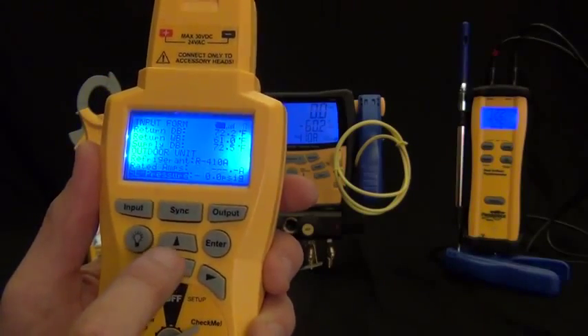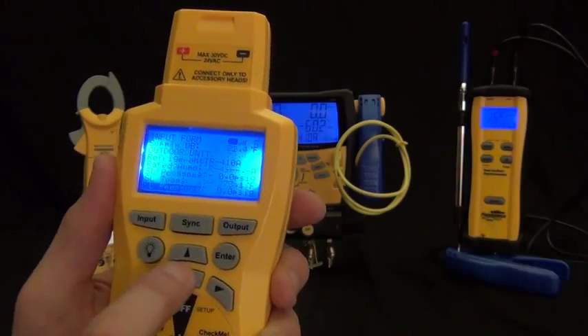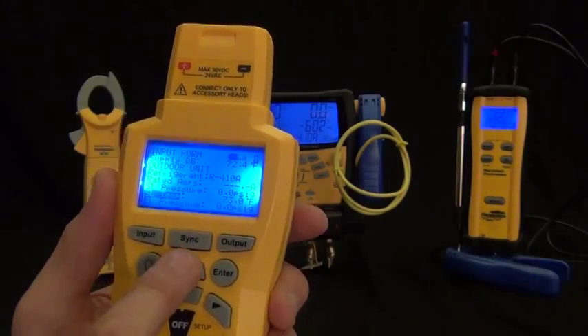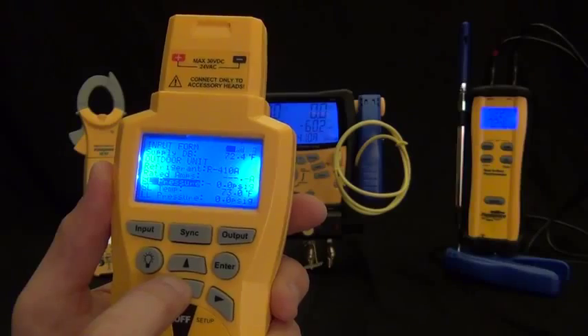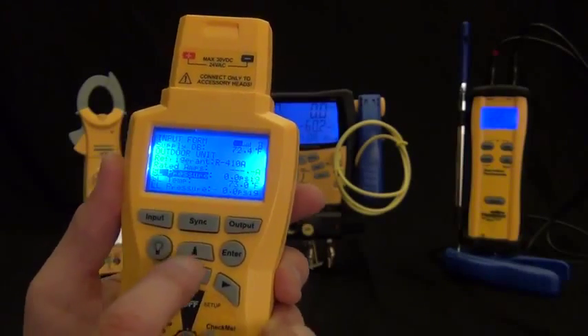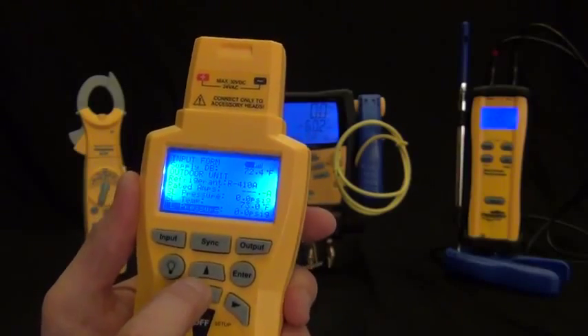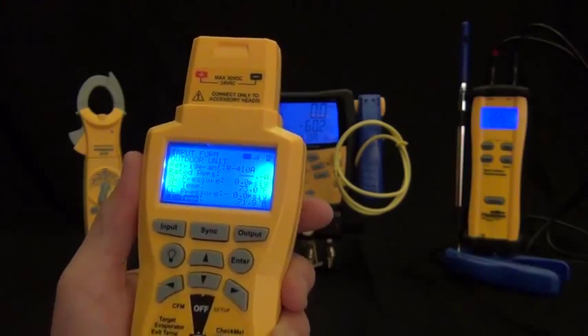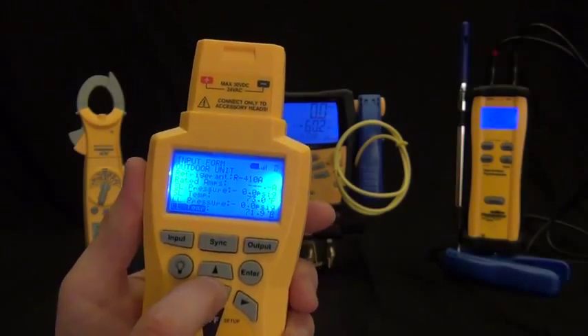Then we got rated amps that actually just be pulled off of the system itself. And then for the SMAN4 we're also doing suction line pressure and suction line temperature. Those are for your superheat calculations. Then we got liquid line pressure and liquid line temperature. Those are for your subcooling calculations.